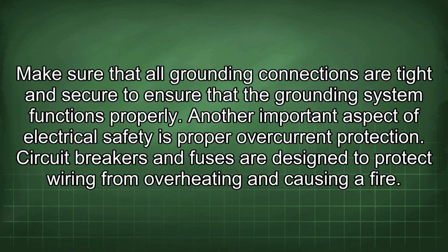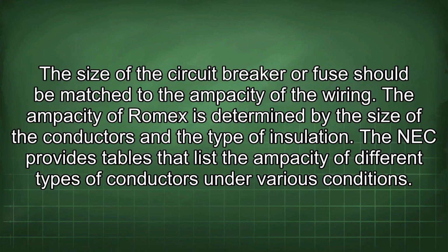Make sure that all grounding connections are tight and secure to ensure that the grounding system functions properly. Another important aspect of electrical safety is proper overcurrent protection. Circuit breakers and fuses are designed to protect wiring from overheating and causing a fire. The size of the circuit breaker or fuse should be matched to the ampacity of the wiring.